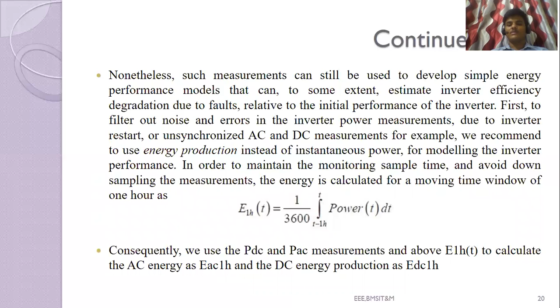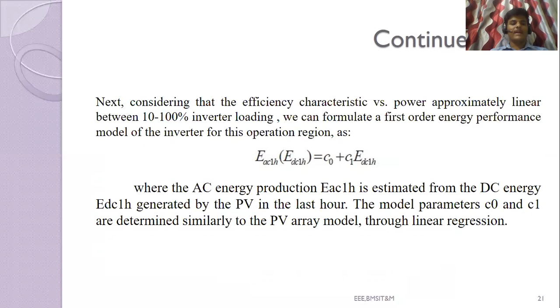Next, considering that the efficiency characteristic versus power is approximately linear between 10% to 100% inverter loading, we can formulate a first order energy performance model of the inverter for these operation regions, given as EAC1H of EDC1H is equal to C0 plus C1 EDC1H, where the AC energy production EAC1H is estimated from the DC energy EDC1H generated by the PV array in the last hour. The model parameters C0 and C1 are determined similarly to the PV array model through linear regression.